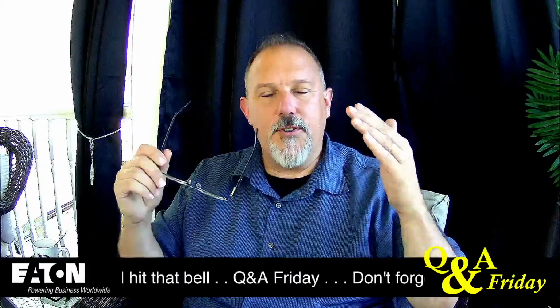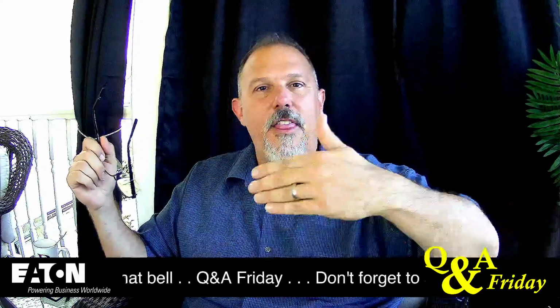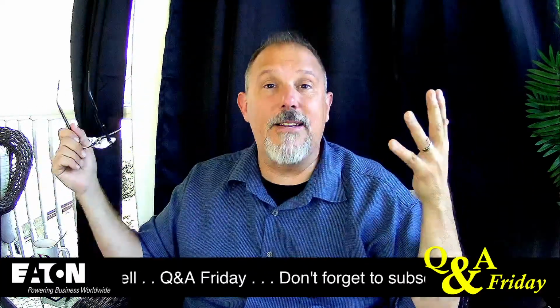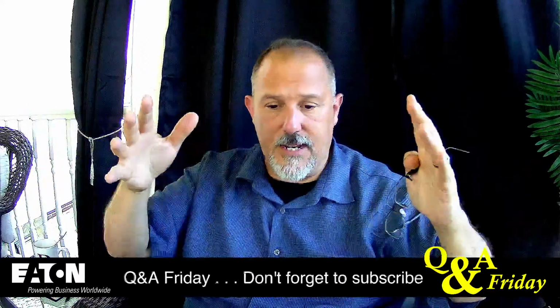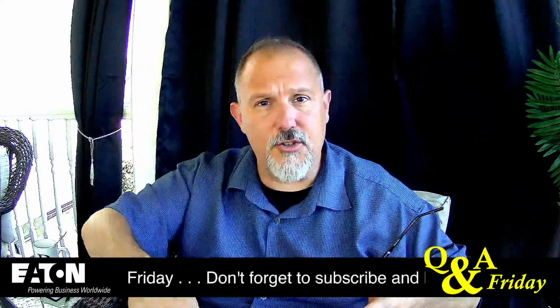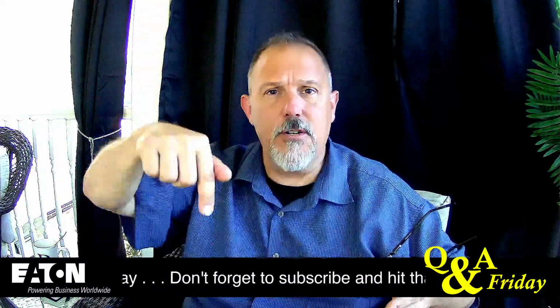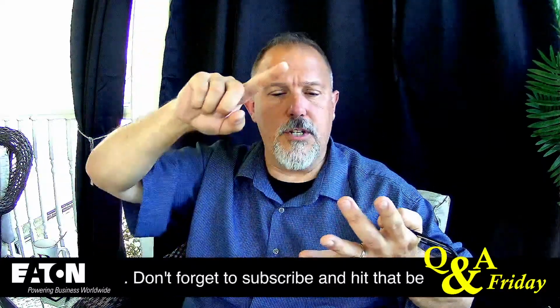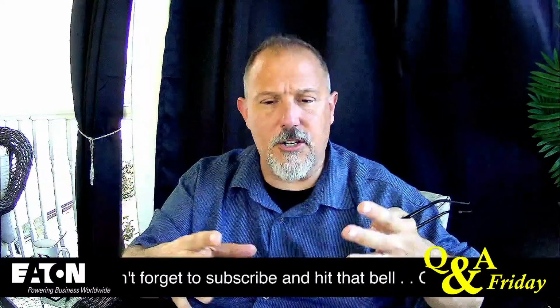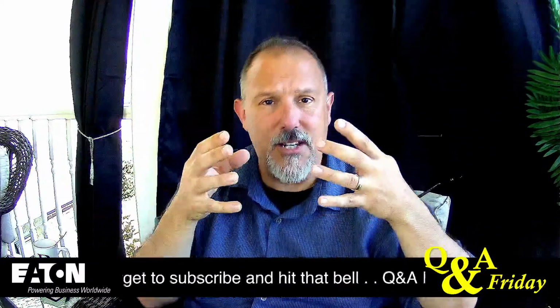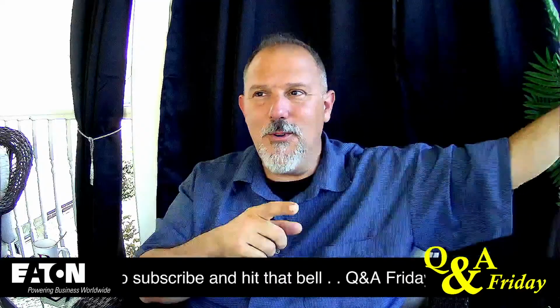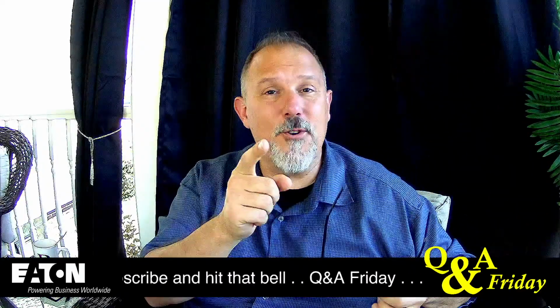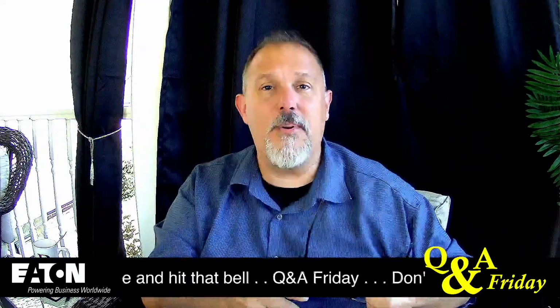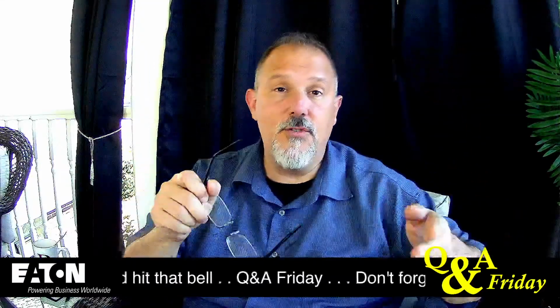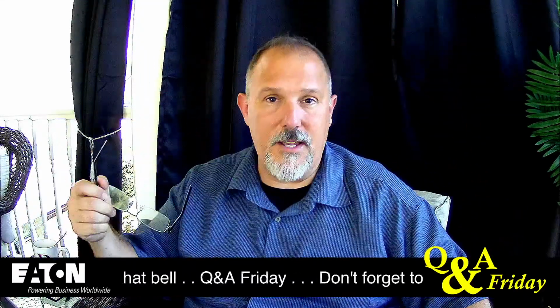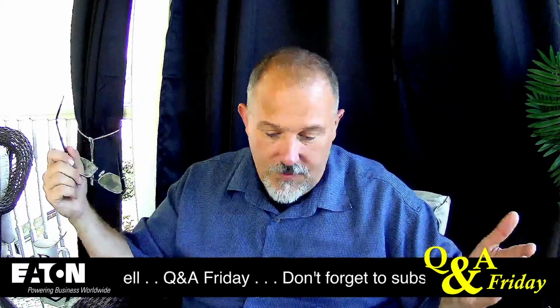If you think about it, you're coming from the utility, you don't have an equipment grounding conductor because you're bonding everything inside of that service equipment. You're establishing your grounding electrode. You have your grounding electrode conductor, and that's bonded to your neutral. It's bonded to the equipment grounding conductor. Everything is at that one spot at that service equipment. But coming from the utility, you don't tie an equipment grounding conductor. That's that grounded conductor that gives you that fault return path back to the utility, and you size that based upon the ungrounded conductor.